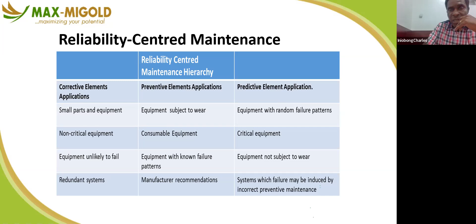Equipment not subject to wear can be placed on predictive maintenance. It's not wearing, and physically you are not seeing what is going bad, but if you have a monitoring device, sensors, and other things, you'll be able to know that, oh, this equipment is due for maintenance. Systems whose failure may be induced by incorrect preventive maintenance: we said this before. There are some systems where, when you put corrective maintenance around them, you will end up spoiling the system, destroying the system, because maybe you don't have the expertise for that kind of maintenance. So where you are not sure of the expertise, or where it is very critical equipment, you just put it in predictive maintenance. Hereby you have devices that can give you readings and all that.